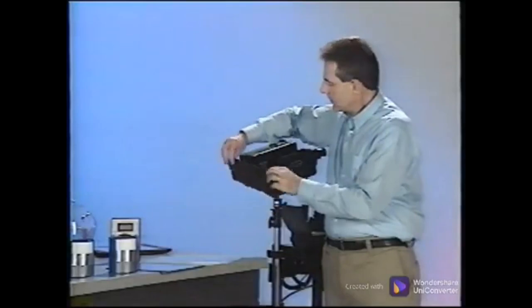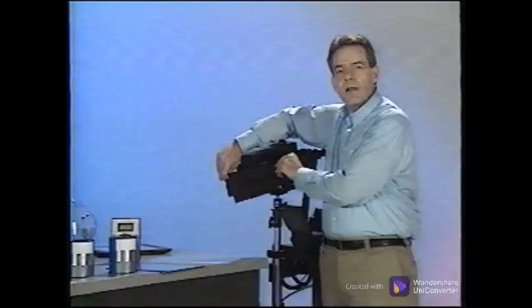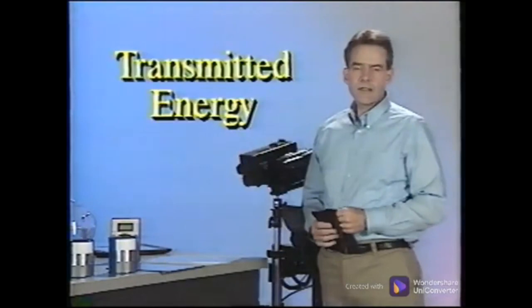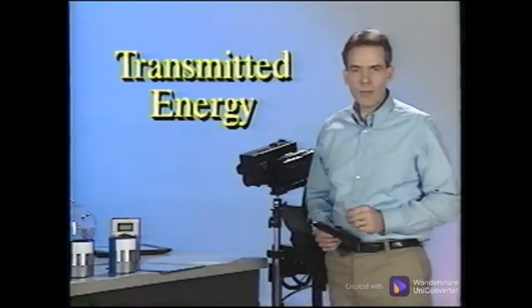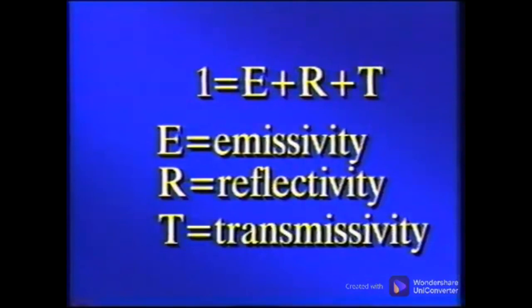Each time the plastic is doubled, less of the image is apparent, that is, less of the infrared energy is transmitted through it. Like emissivity, this transmitted energy must be compensated for in order to produce accurate temperature measurements. Now the formula must include this transmitted energy, so the complete formula is 1 equals E plus R plus T, where E is emitted energy, R is reflected energy, and T is transmitted energy.